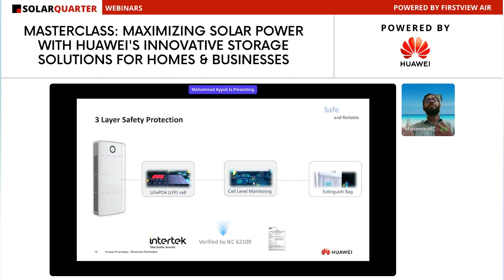As a last option, we have added an extinguishing bag. So the chemistry is safe, we have monitoring at the cell level, necessary circuit breakers and protection inside the product, and on top of that an extinguishing bag. If after all these components there is still a fire due to some issue, the extinguishing bag helps extinguish the fire and control its propagation to adjacent areas.